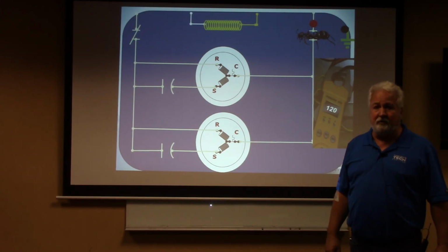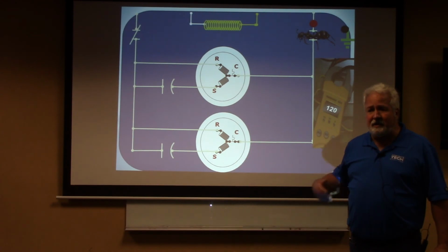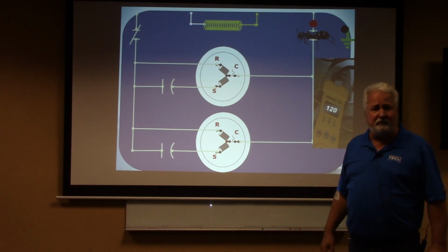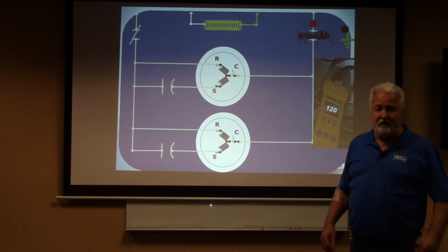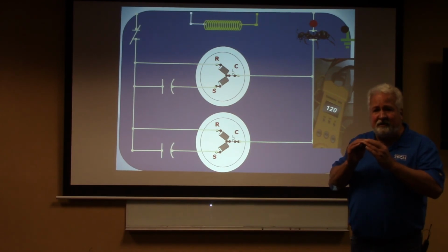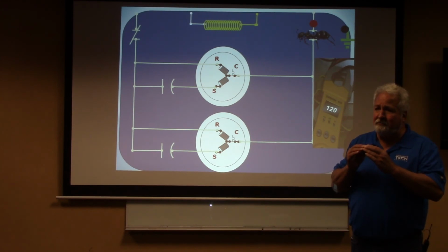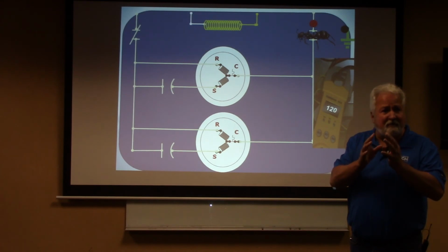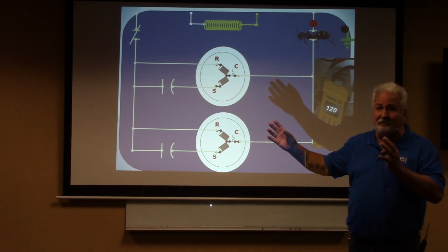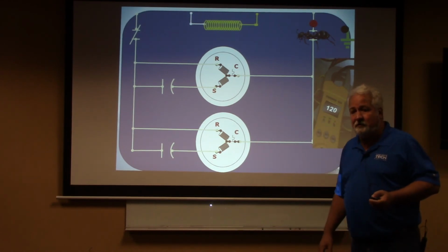It's huge in your business. And don't start reading across switches with your own meter just to see, because if you're using that continuity deal, you can still have continuity and still be dropping some voltage. Does that make sense? If the contacts are dirty, is that a resistance? Is that going to produce magnetism or heat? Magnetism. Heat, is that right? So if we're producing heat here, that means we got some of the voltage being dropped here, but then there's going to be some other things that are not going to see all that voltage. Does that make sense? Good, so good.